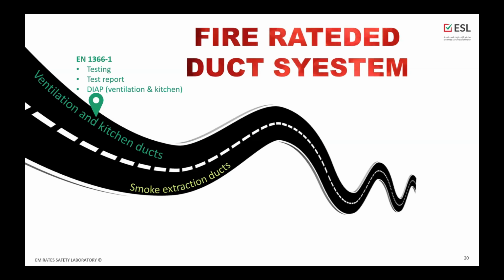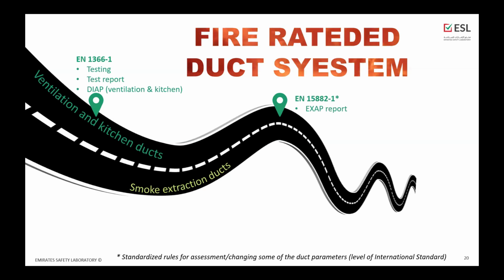We are doing the test, we are issuing the test report, which has the direct field of application of the test results. This is something unique for EN. After that, you can use the standardized rules for assessment or changing some parameters across the duct construction, which ends up with the EXAP report, and then those two types of reports are combined by the classification report, giving you the wide combined application as well as a rating in terms of the classes. And then there is a certificate.